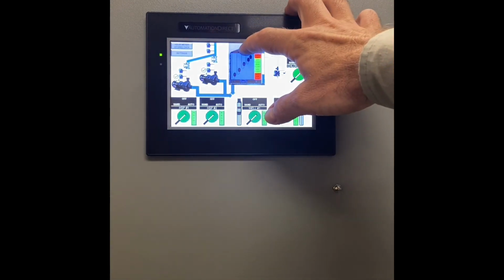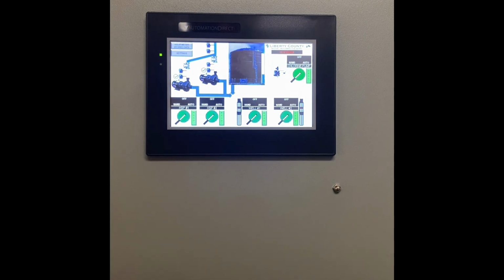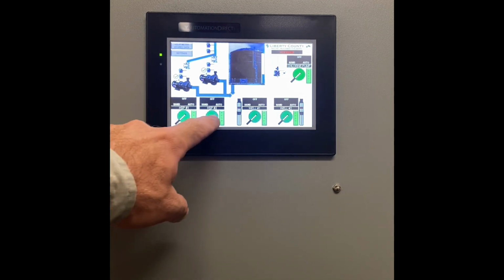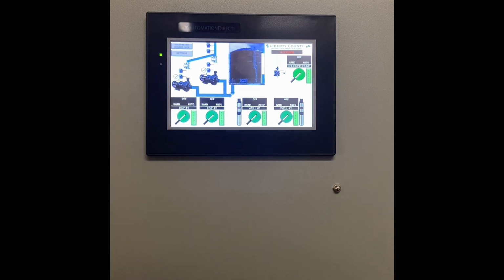If I touch the groundwater storage tank, that pop-up window will also disappear. I like to have a lot of information available without completely cluttering the screen, so pop-up windows are an excellent method to do that. Now, working our way down to the bottom left, we have the high service pumps 1 and 2. Switches work exactly the same as the chlorine. And then we have the wells 1 and 2 with their respective controls and indications.